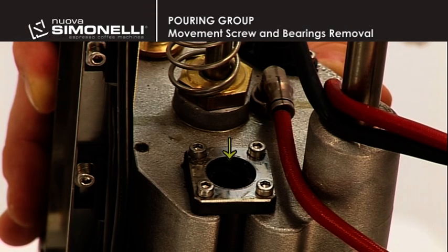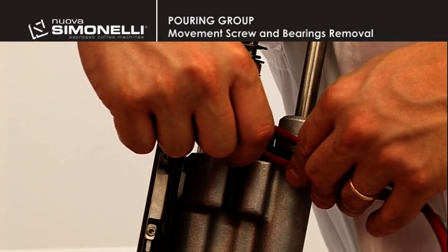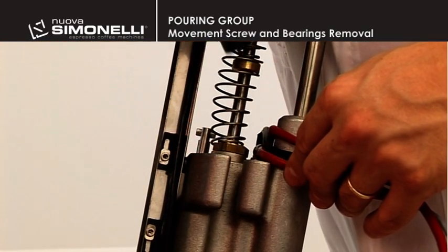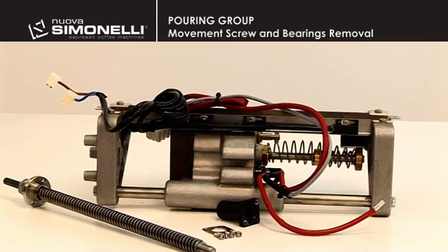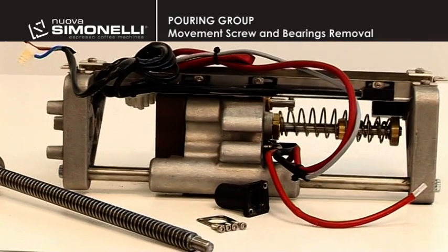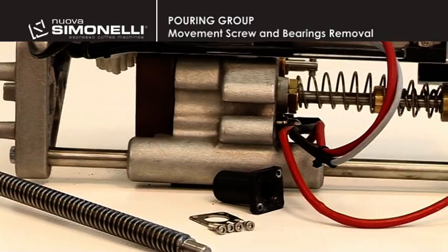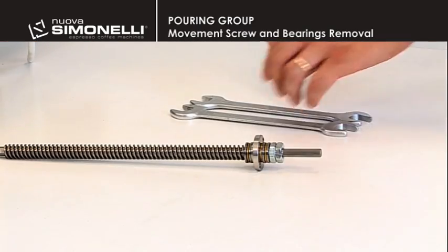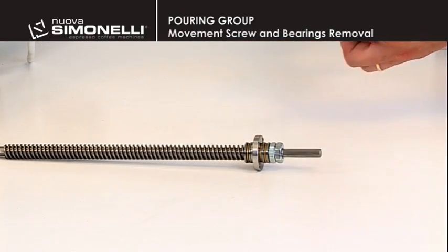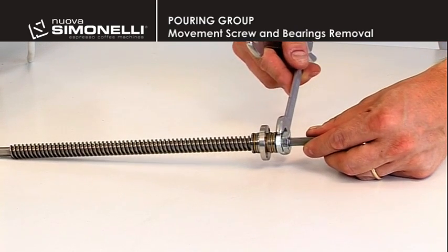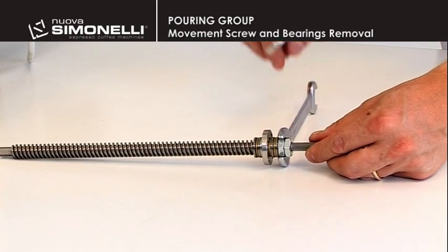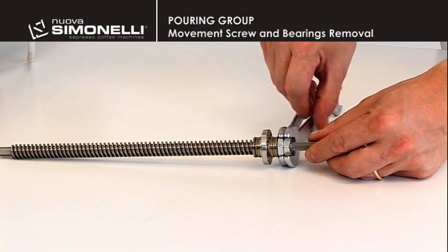The worm screw is located in the right-hand side of the infusion chamber. To remove it, loosen the four 2.5mm Allen screws. The bearings are part of the worm screw. To replace or clean the bearings, remove the nut and support nut using two 17mm wrenches.